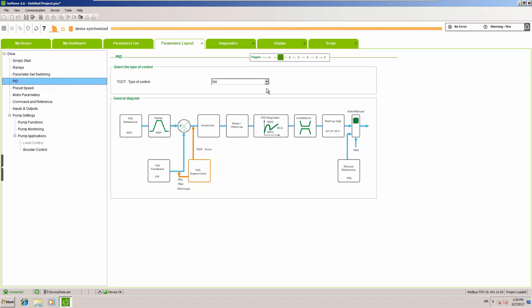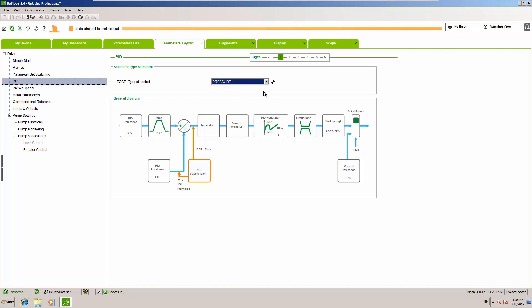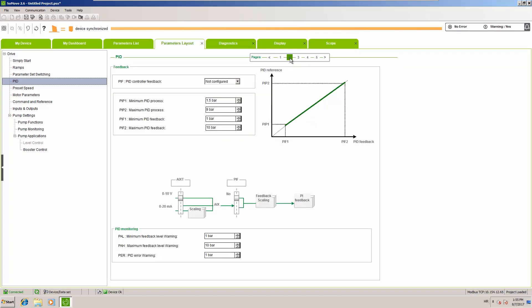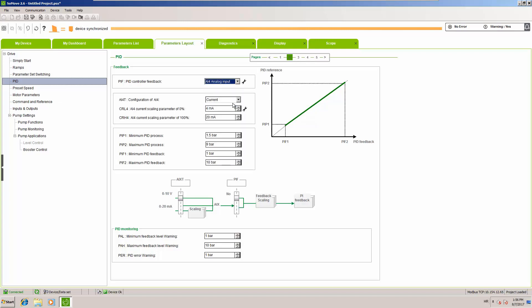For the type of control, we will set up pressure regulation. First, select pressure — we are going to have pressure regulation with our drive. Our feedback is the pressure sensor on the output. Analog input 4 is our feedback, with 0 as minimum and 10 bars as maximum feedback.